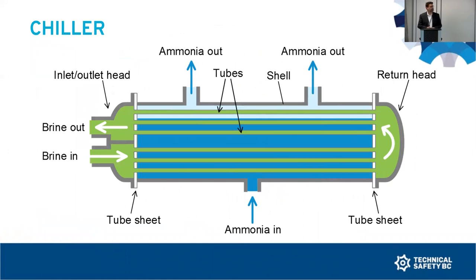So here is a simple diagram of a chiller, a shell and tube chiller that is typical of what was being used at the Fernie Memorial Arena. These are quite common in this application. I won't describe exactly how it works, but what's important is that when we understood the magnitude of what had occurred within the room, there was a lot of speculation as to where the failure within the chiller had occurred and what was the nature of the failure. Most would have thought that there was a very large failure below the liquid level within the chiller. That was thought to be the most likely reason you could get such a dramatic effect within the room, such a large and sudden release with such a devastating impact. And the reality of what we found was the opposite.